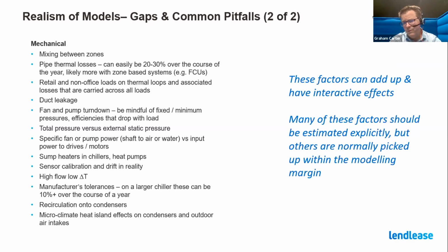And then the last 3 points are a little bit of a collection of what can happen with something like an air-cooled chiller, let's say, where there are manufacturers' tolerances that you need to be aware of, and they can add up. They can be more than 10%, and the manufacturer is allowed to supply you that equipment with that less than nominal efficiency and still be within spec and within standards. So you just need to be a little bit careful of that.